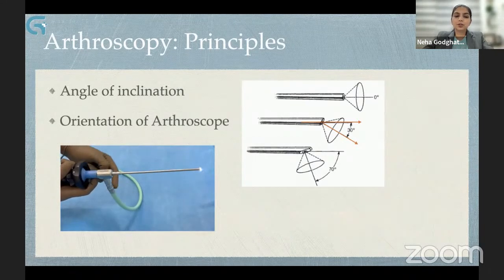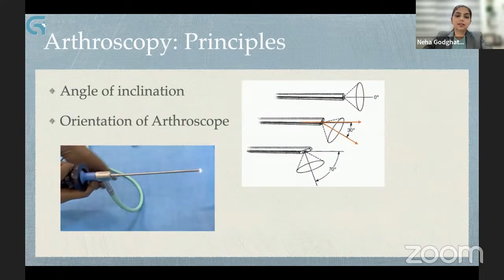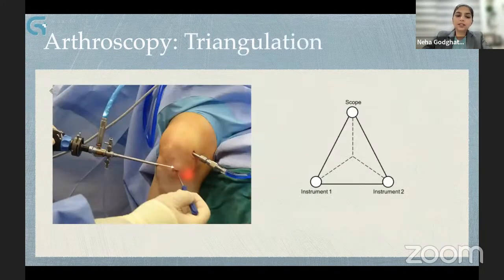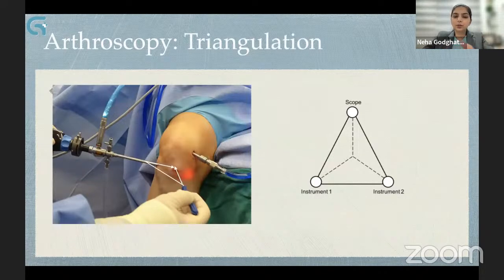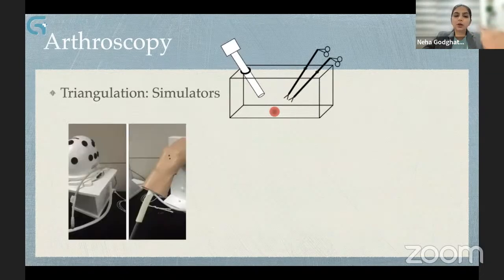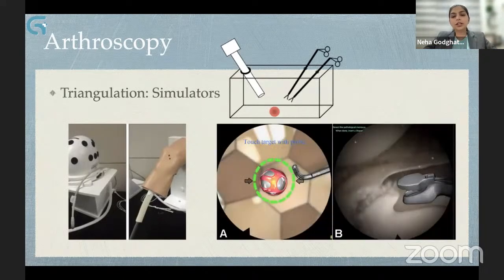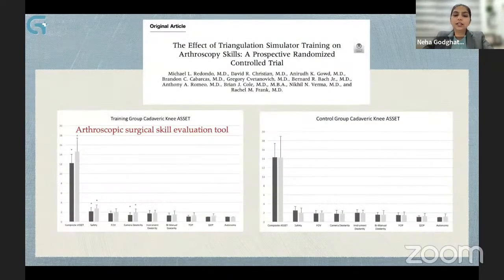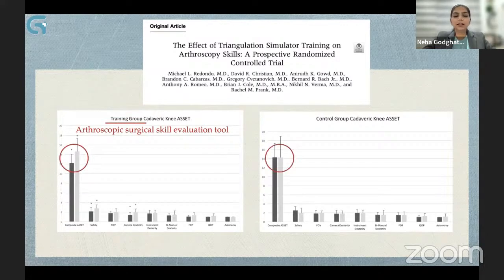Important concepts in arthroscopy: the angle of inclination is the angle between the axis of the shaft of the scope and the perpendicular axis of the lens. The commonly used arthroscope in knee arthroscopy is 30 degrees. The direction of the light cable is exactly opposite to that of the scope lens — this helps in getting orientation of where the scope is inside the joint. Triangulation is the core competency needed in arthroscopy: the tip of the instrument should be visualized in front of the lighted area on the video monitor. Currently, a plethora of arthroscopic trainers are available ranging from low-fidelity non-anatomical models to high-fidelity virtual reality systems. Prospective randomized controlled trials have shown that after training residents on simulators, their cadaver knee ASSET scores increased significantly compared to controls.